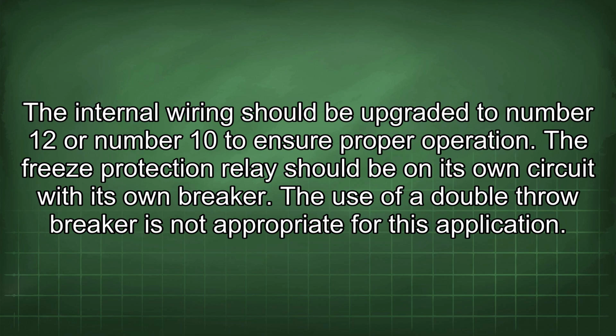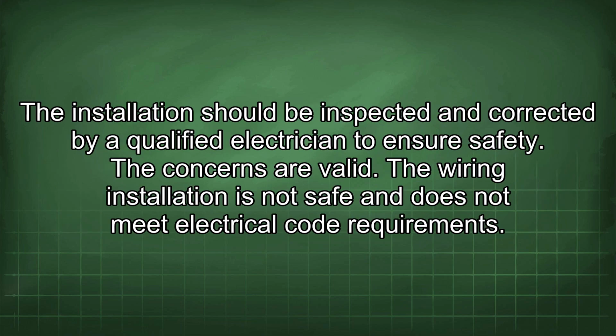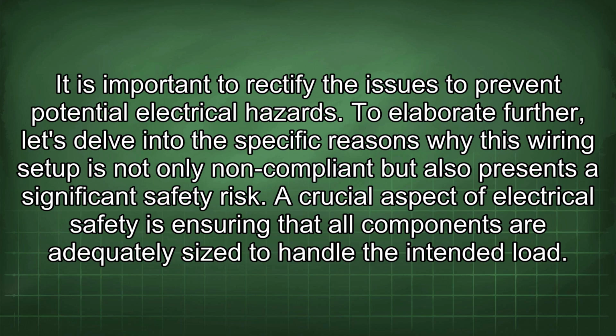The freeze protection relay should be on its own circuit with its own breaker. The use of a double throw breaker is not appropriate for this application. The installation should be inspected and corrected by a qualified electrician to ensure safety. The concerns are valid. The wiring installation is not safe and does not meet electrical code requirements. It is important to rectify the issues to prevent potential electrical hazards.